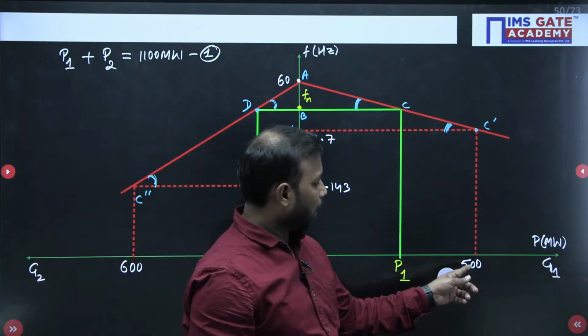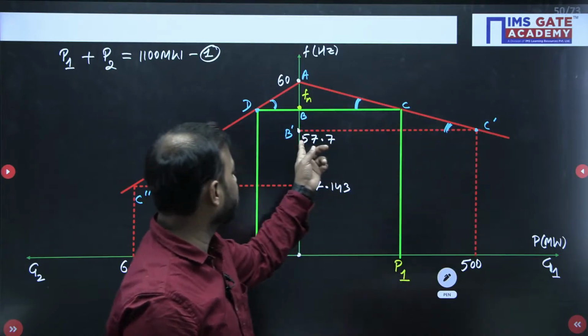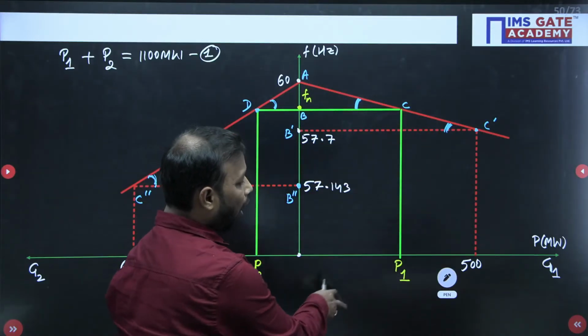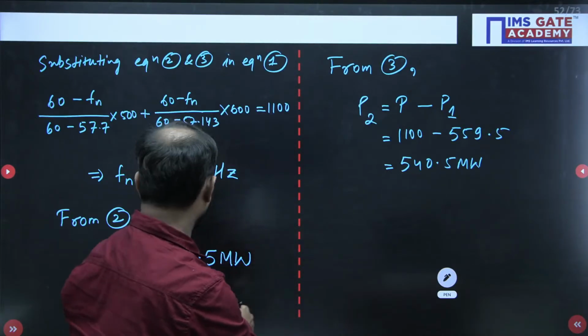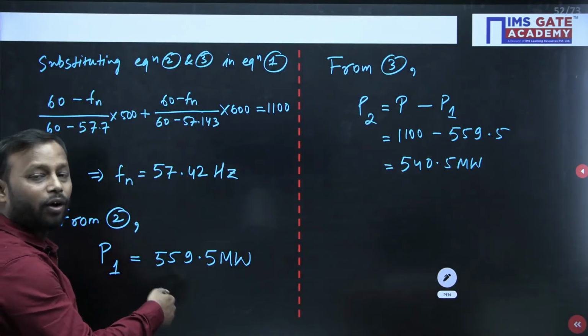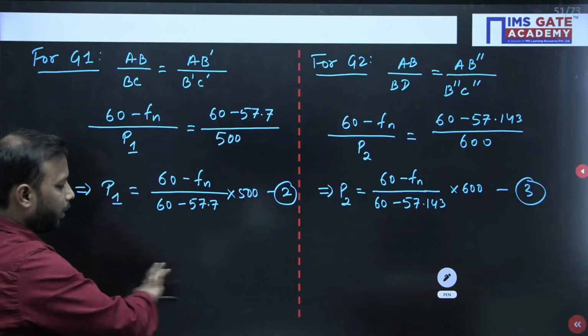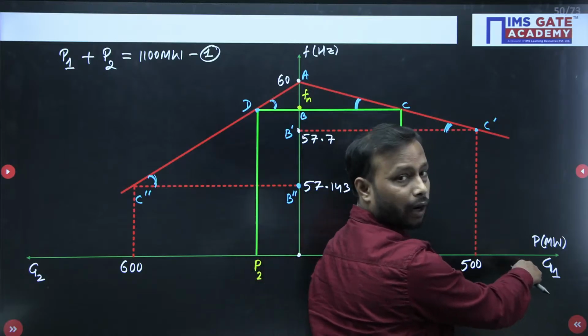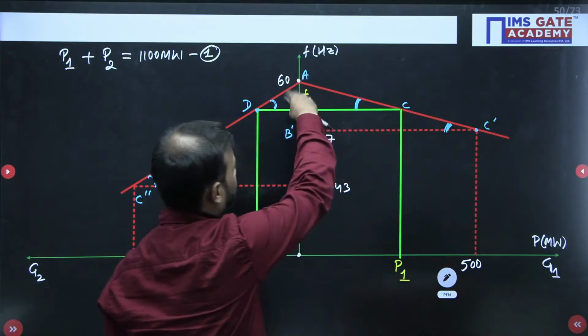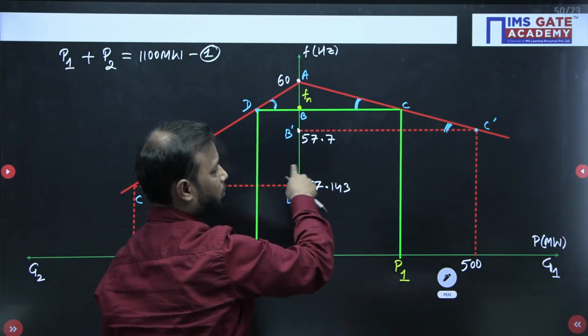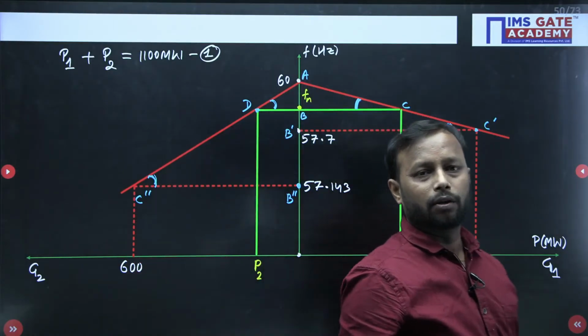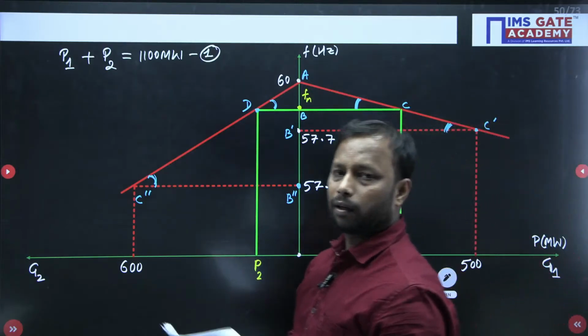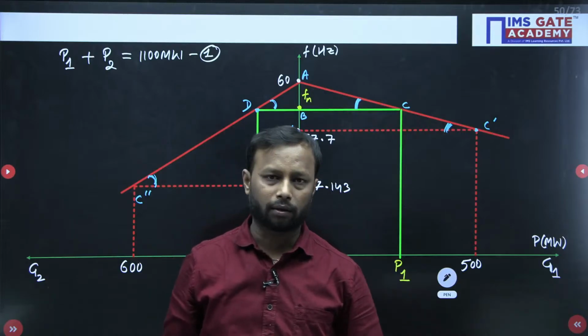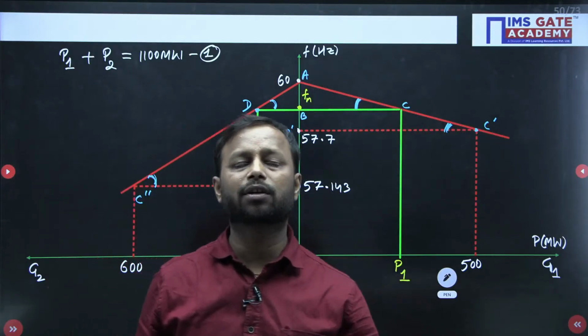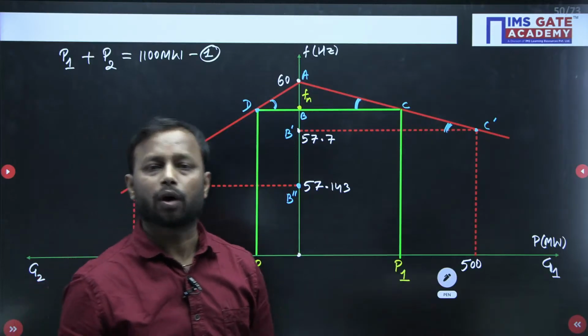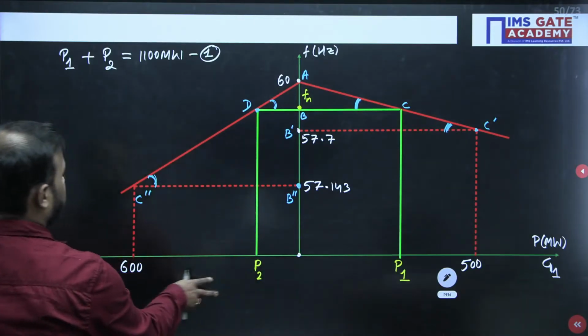At 500 for generator 1, the frequency is 57.7, but generator 1 is actually delivering more than its capability, around 559.5, so frequency will reduce further from that point. So it is evident that whenever you try to increase the load, frequency is going to reduce. Let us move on to the next problem.